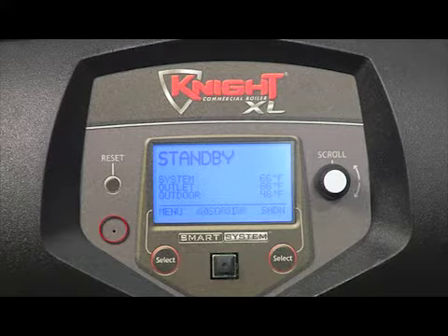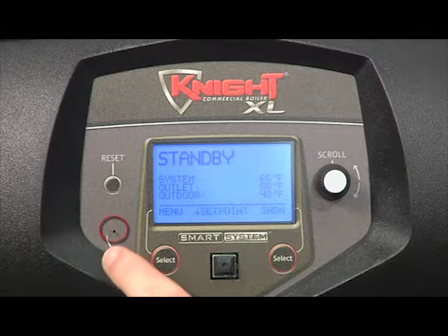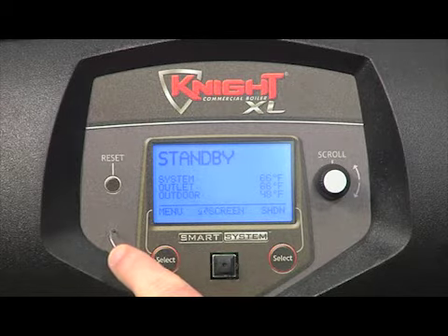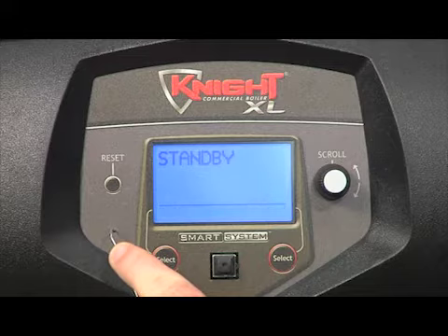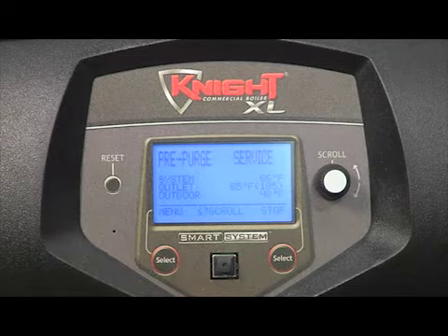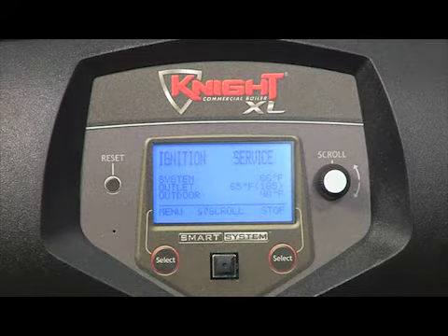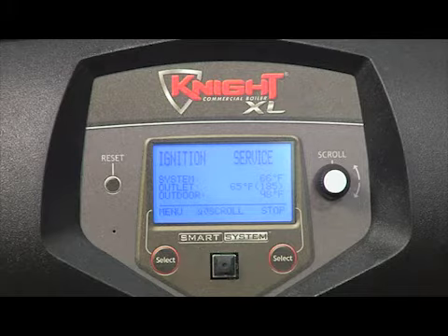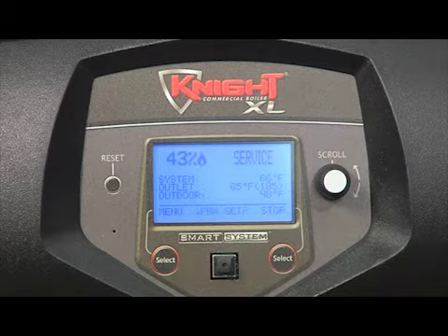Locate the pinhole button on the display. Using a paper clip or something similar, press and hold the button for 5 seconds. The word Service will appear on the status line of the display. The unit will fire at its normal ignition speed and will then modulate its firing rate to 100%.